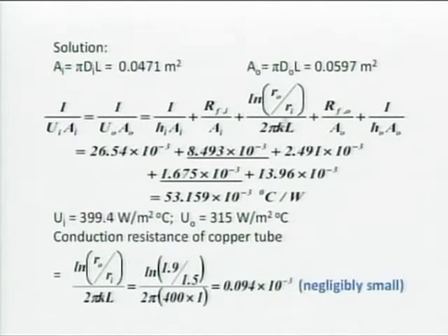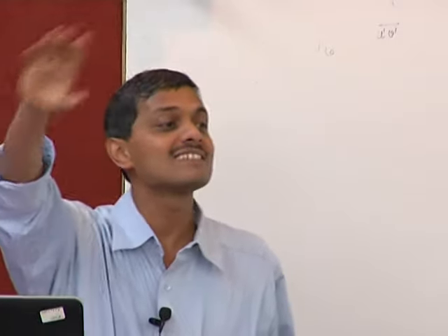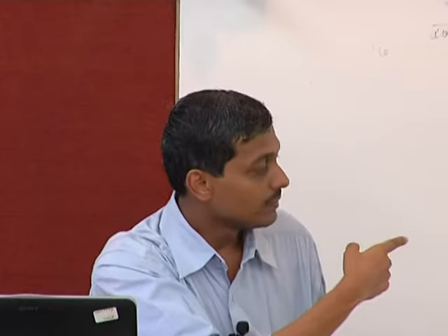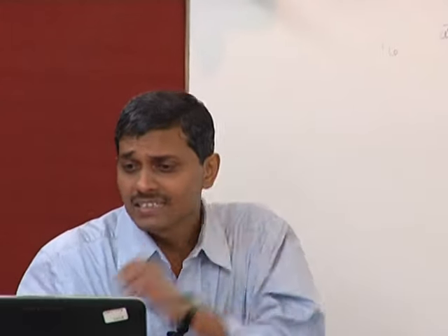Through this problem, I want to show h_i·A_i, h_o·A_o, and the conductive resistance. I have taken a stainless steel tube with k = 15. If I change to copper, k goes up to 400 and the conductive resistance becomes one order less — here it is 9×10⁻³, and with copper it becomes 0.094×10⁻³. That is why in refrigeration all condensers and evaporators are made of copper tubes. Material selection is the biggest issue in heat exchanger design.